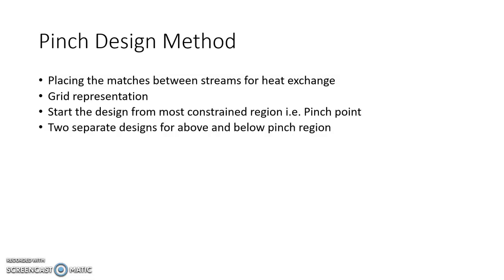First, before we place the matches, we need to represent the problem in the form of a grid representation. We create a grid of streams, as there are two regions — above pinch and below pinch. The above pinch region will be in balance with hot utility and below pinch will be in balance with cold utility. We design above pinch region separately from the below pinch region.